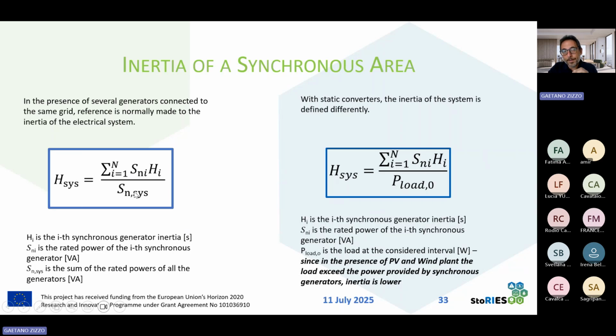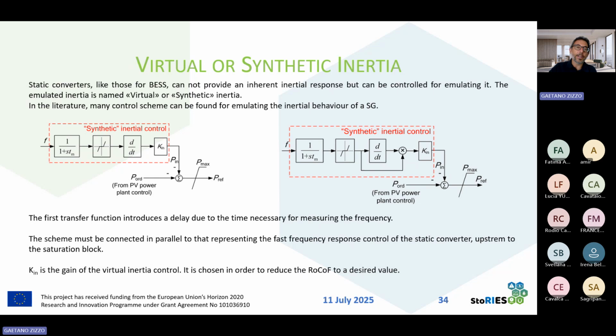Since this sum is calculated only considering rotating machines, if we have a large contribution from wind plants and photovoltaics, P load in the new condition is higher than the sum of the rated powers SN. And so we can say that due to the spread of renewables, the inertia of the system is reducing during the years. And so we must contrast this reduction, and we can do it using, for example, battery storage systems for simulating the inertia of a power plant.